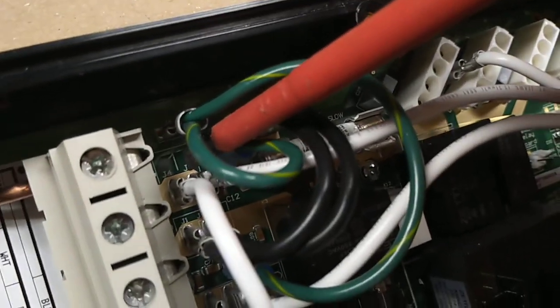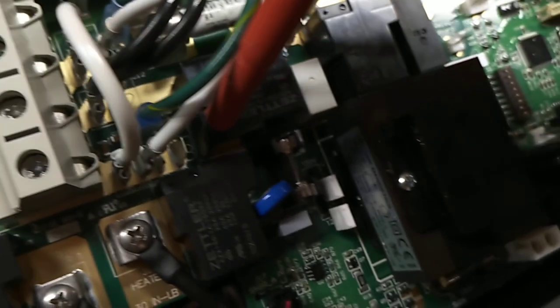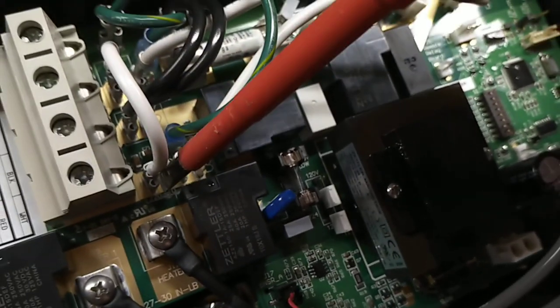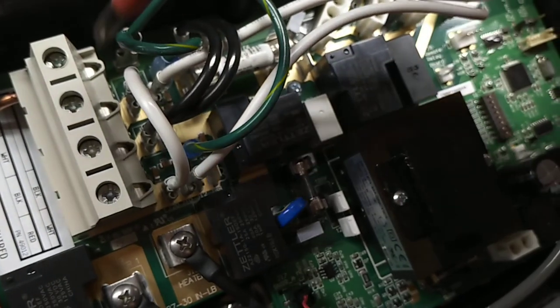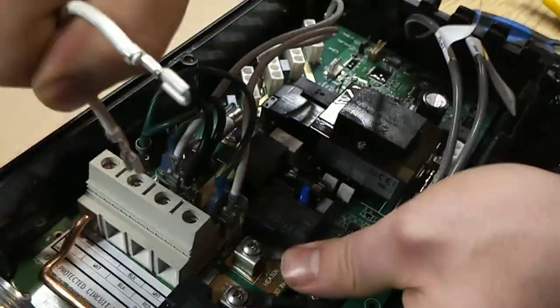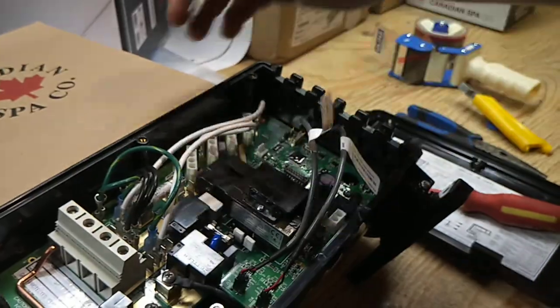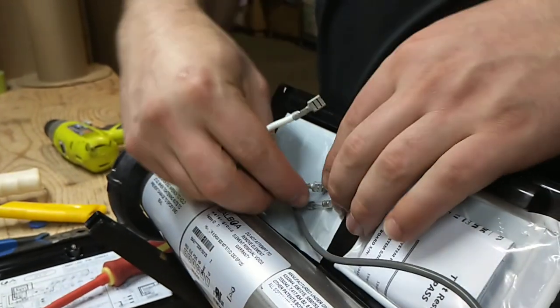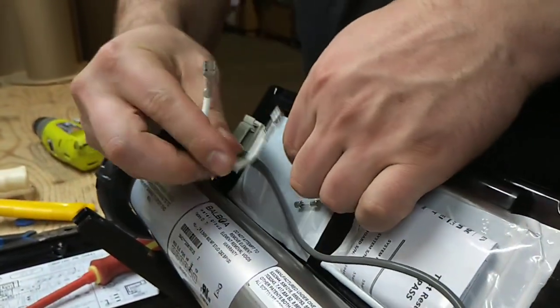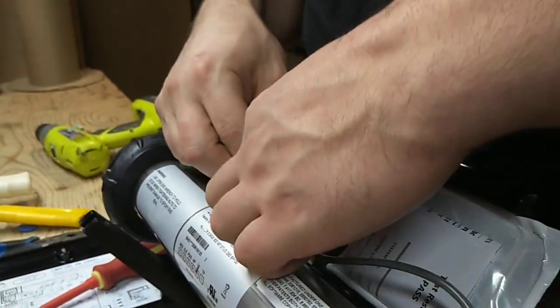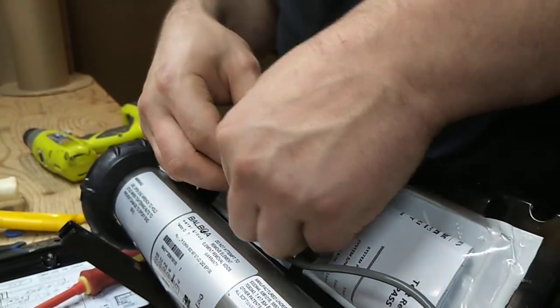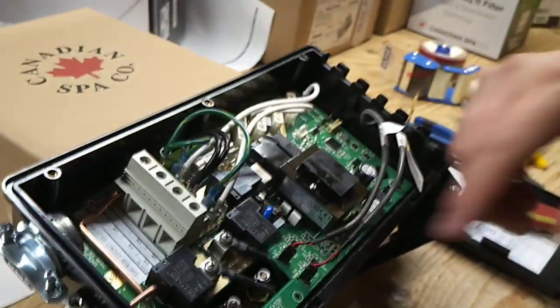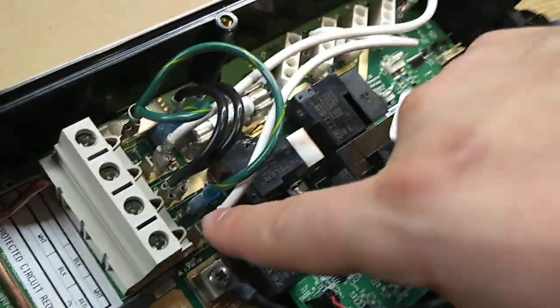You can see it here. See the number one there? Bank one. And if you look down here, bank three. This jumper wire goes from the pins on the connections on bank three to bank one. And we're going to simply wiggle it back and forth and remove this jumper wire. We're going to stick this on the backside here in this little pouch, so in case you ever need to convert it back or you need this jumper wire again, you've got access to it. So we don't lose it. Now you've removed the power from one to three.